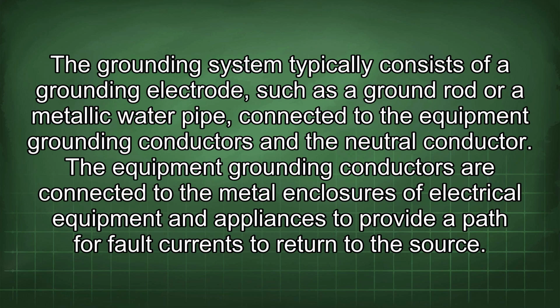The grounding system typically consists of a grounding electrode, such as a ground rod or metallic water pipe, connected to the equipment grounding conductors and the neutral conductor. The equipment grounding conductors are connected to the metal enclosures of electrical equipment and appliances to provide a path for fault currents to return to the source.